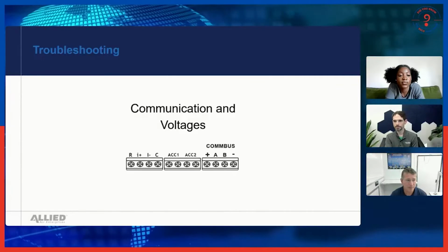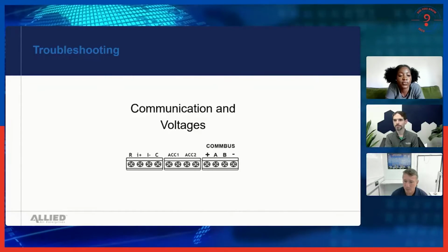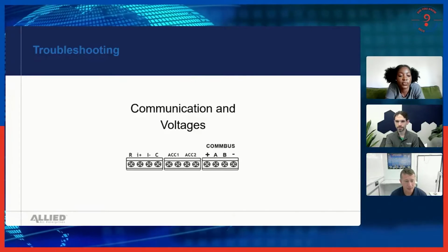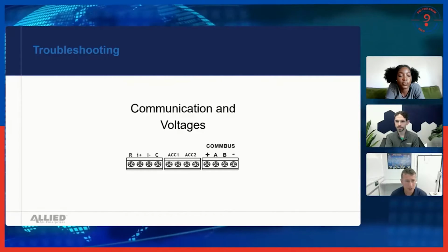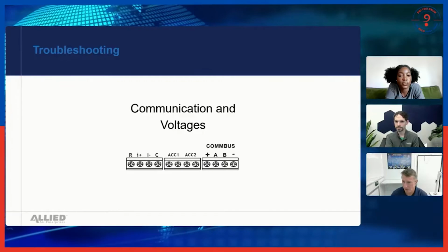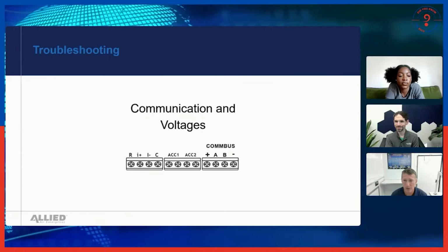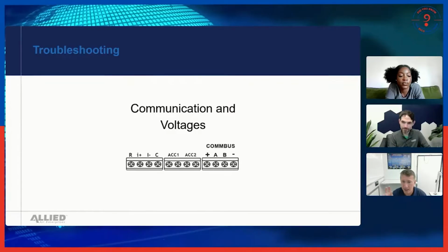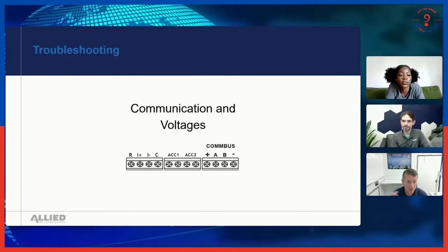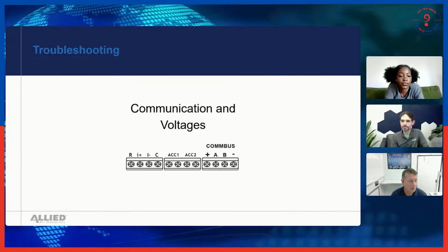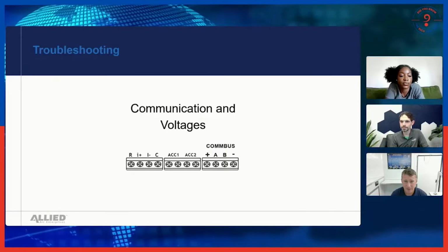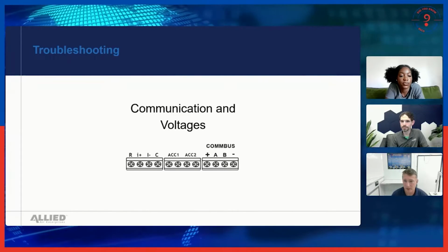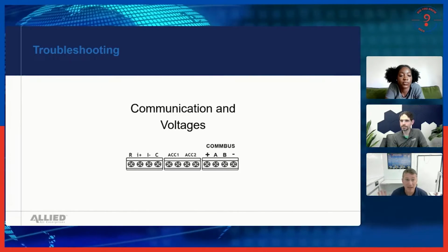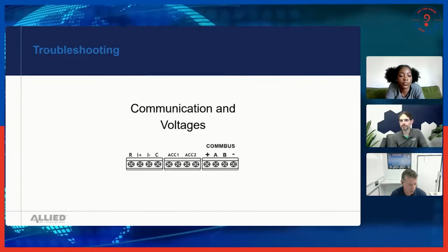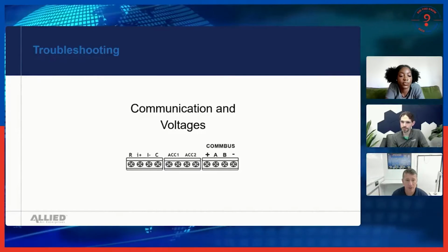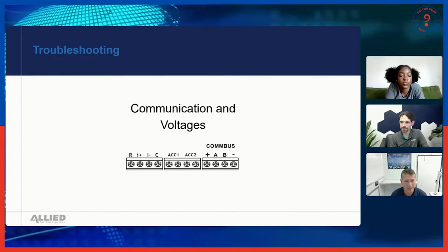I worked with a manufacturer doing a lot of site visits. We had one particular communicating system that worked great most of the time, but the homeowner was having problems with it losing communication, getting an error code on the thermostat saying communication lost, contact your contractor. They got tired of seeing this and wanted new equipment because they thought it was faulty, since the rest of the time it ran great. So I pull up to the home getting ready to evaluate what this potential problem could be.